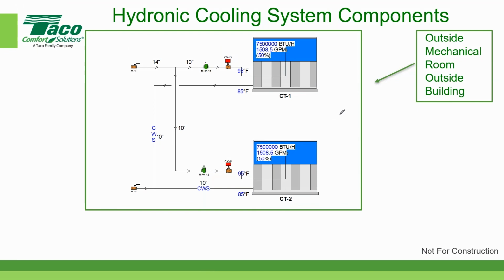so the International Energy Conservation Code, or IECC, does not recommend using basin heaters for cooling towers because they're wasting electricity. But typically the basin heaters are electric resistance heaters that are in the base of the cooling tower. And then the piping itself is heat traced, which means that right along the outside surface of the pipe, we put resistance heaters, and then we cover those resistance heaters with insulation. And that's how we keep the piping from freezing.